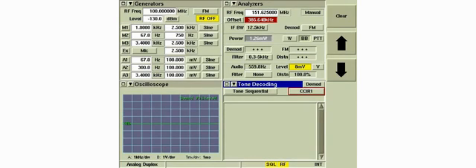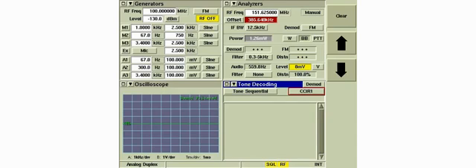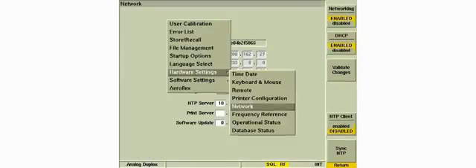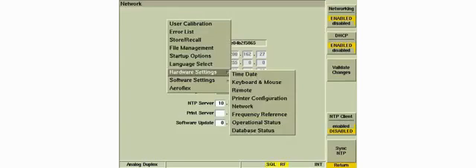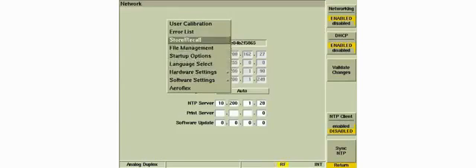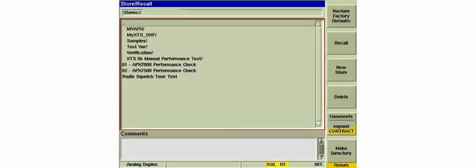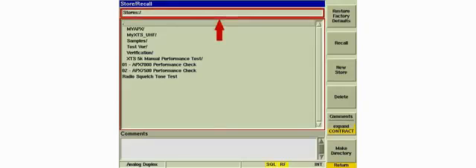In this example, the instrument is programmed with all of the settings for a specific radio test and the settings are ready to be stored. The store recall tile is accessed through the Utilities menu.